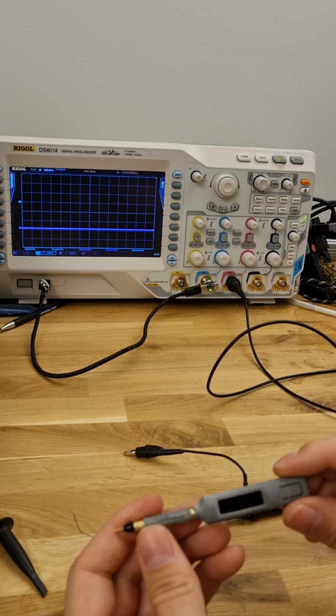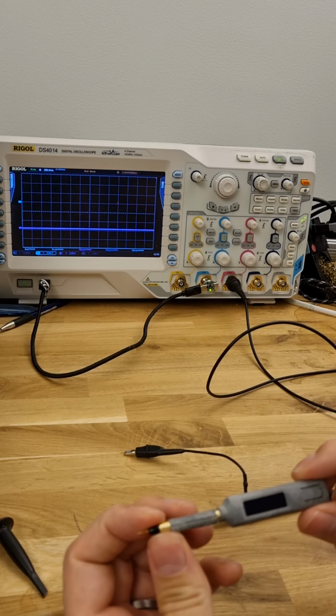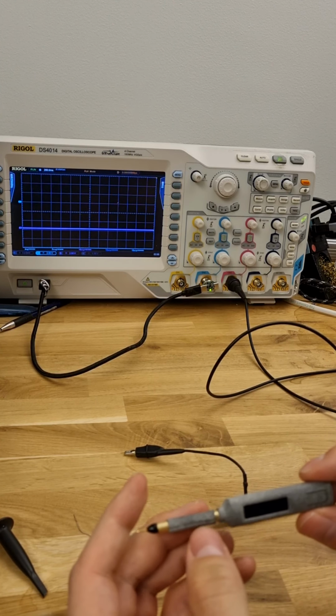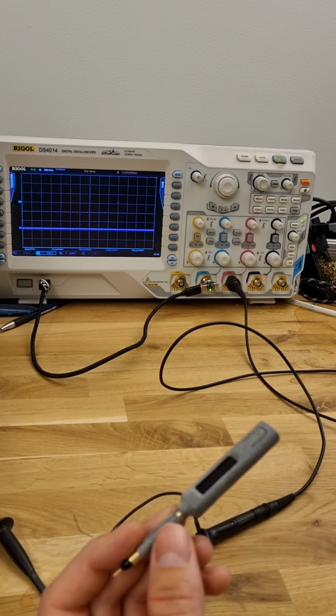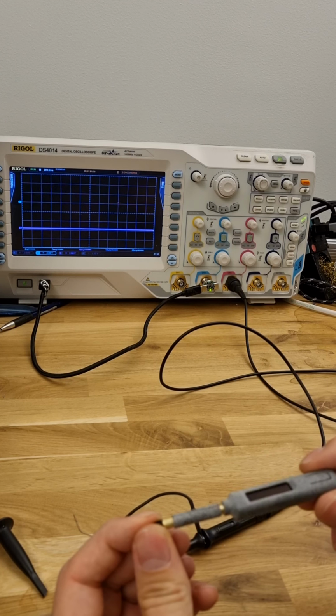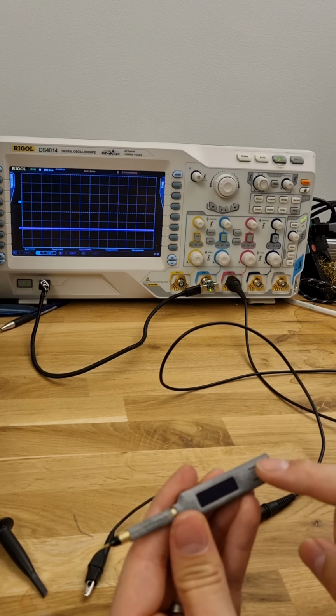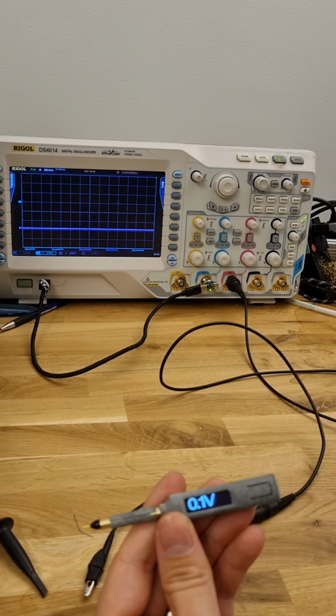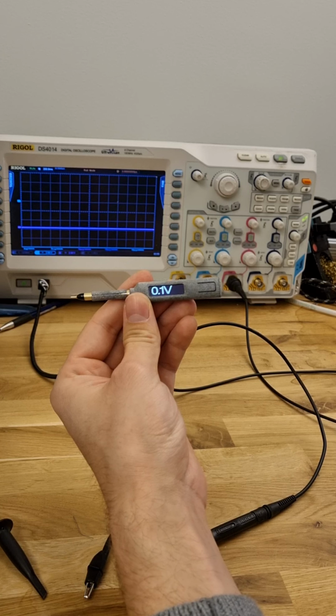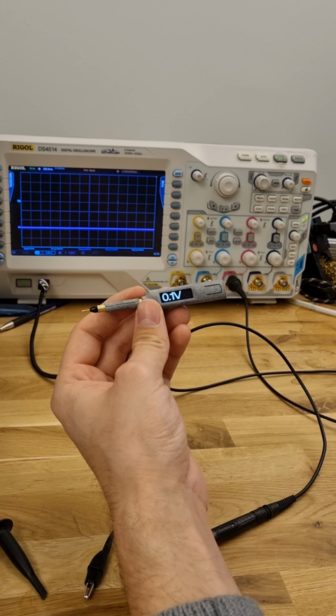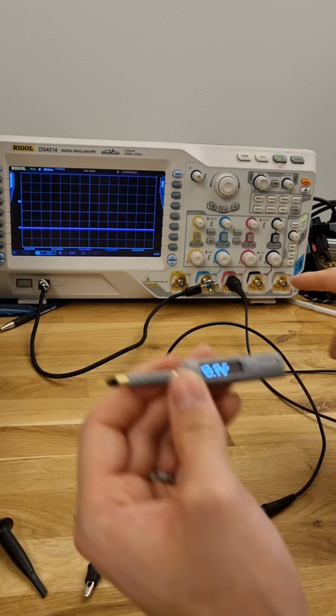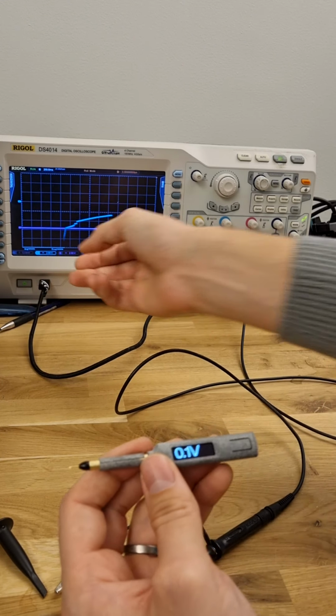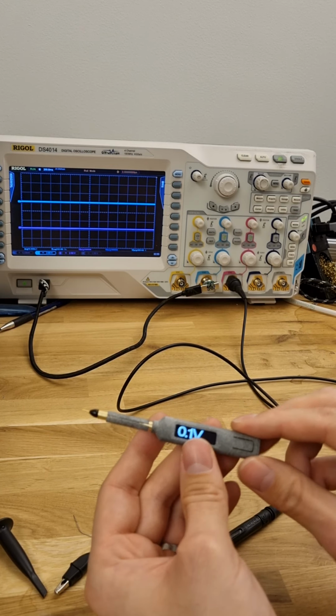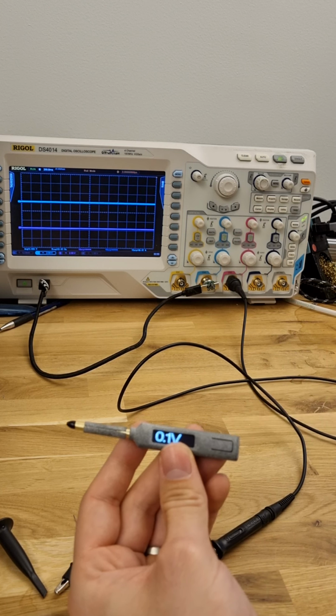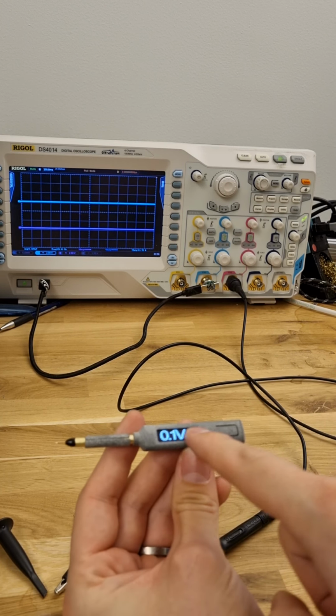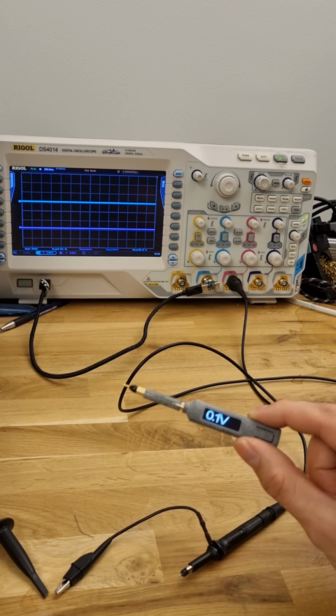The vprobe can be used when you want higher isolation, or when you want just less cables, or when you want to have the probe farther away from the scope. So let's turn it on. First, the product scans for the most empty frequency and starts transmitting on that frequency. And now the product is transmitting to the receiver. So let's sync the receiver by just turning it on and off.